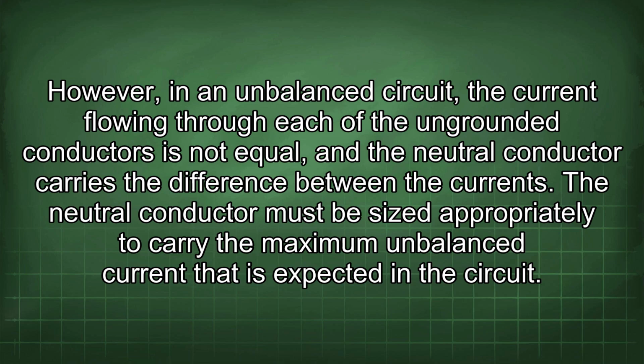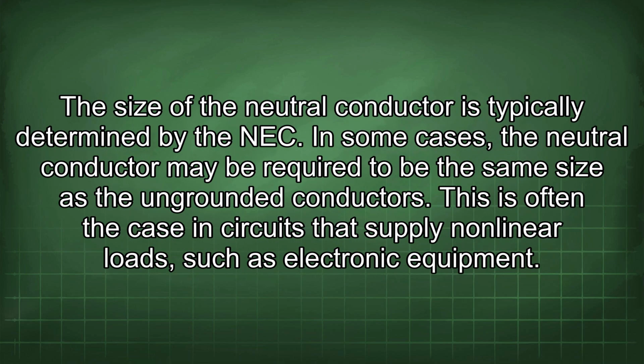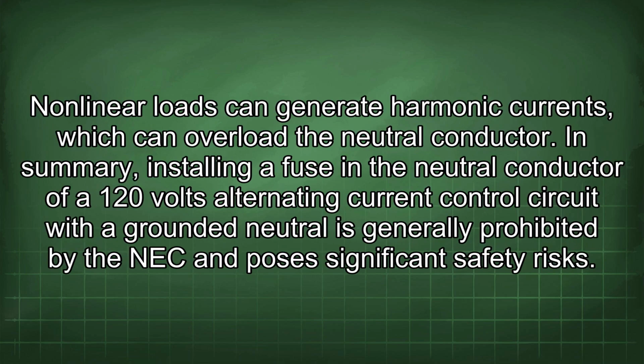The neutral conductor must be sized appropriately to carry the maximum unbalanced current that is expected in the circuit. The size of the neutral conductor is typically determined by the NEC. In some cases, the neutral conductor may be required to be the same size as the ungrounded conductors. This is often the case in circuits that supply nonlinear loads, such as electronic equipment. Nonlinear loads can generate harmonic currents, which can overload the neutral conductor.